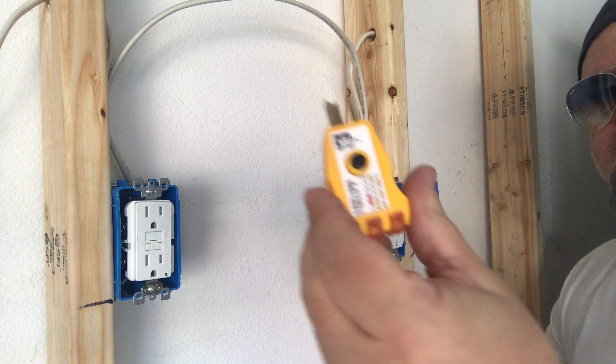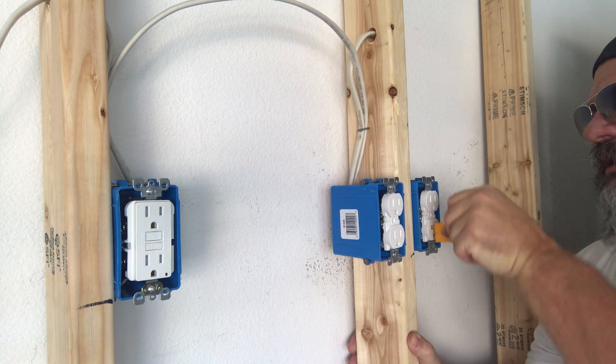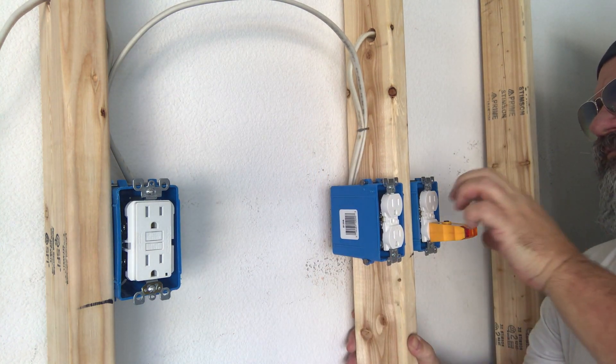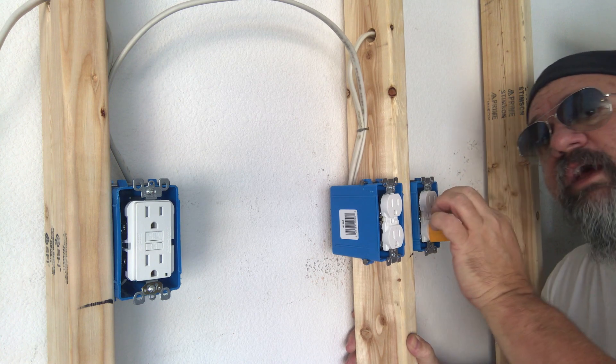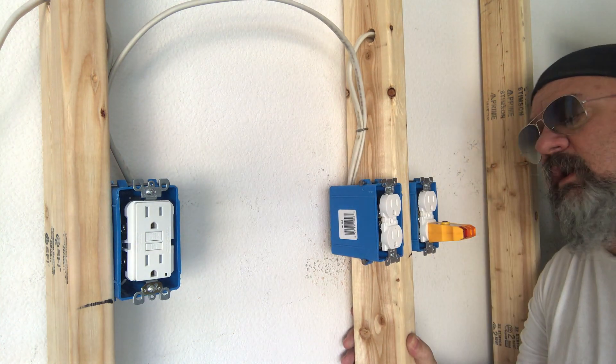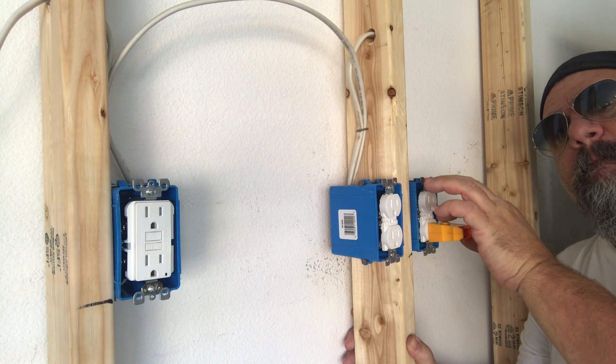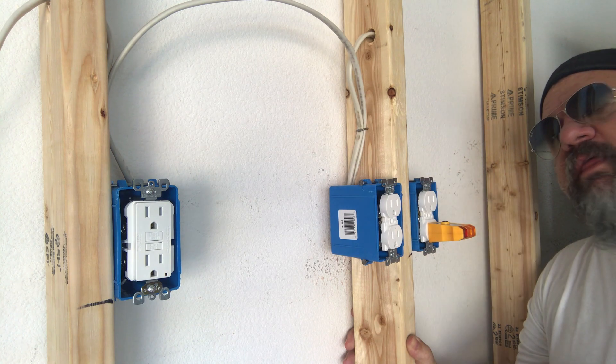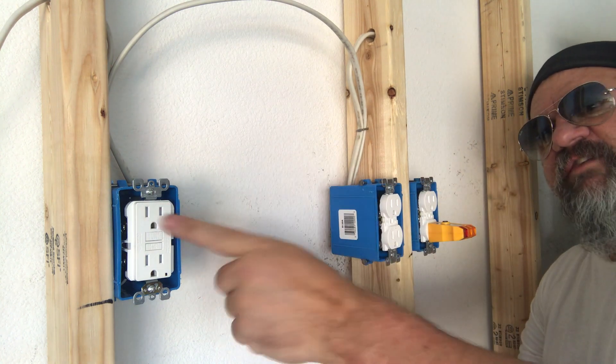Now how do we test it to know if we're GFI protected? Well there's a little test button right here on top of this. And it trips it to ground, the neutral to the ground, not hot to ground. If it was hot to ground you'd have a big arc. So let's test it. Since that shut that GFI off, everything in that circuit is now de-energized.